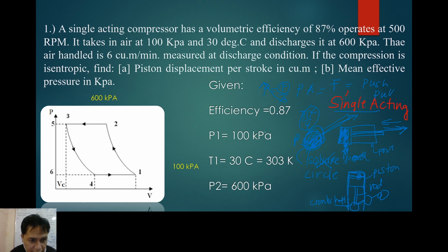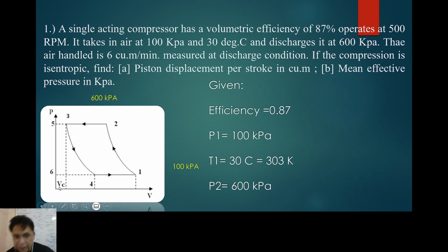So yung refrigerant pressure is here, and there's an area here, so the piston will go forward. But then, in the return, the refrigerant will not come here, no? Kasi single acting lang eh. So it will be returned by either spring or other mechanism. So that's the meaning of the single acting compressor. Now I'll repeat, single acting compressor is a type of compressor that the refrigerant is acting only on one side. Now, sa malinaw na, this is clear, huh?